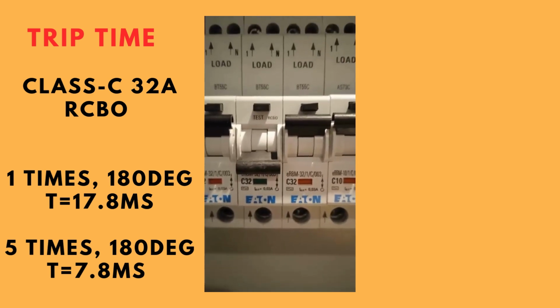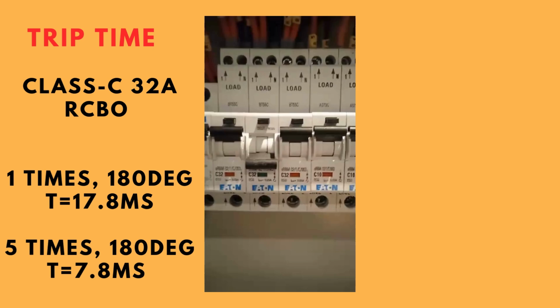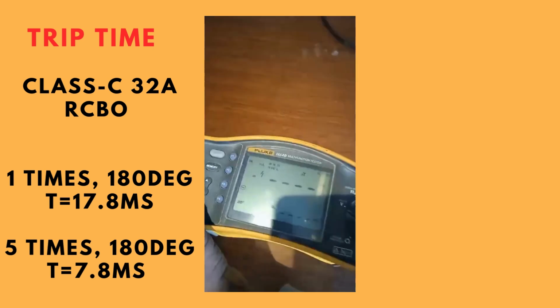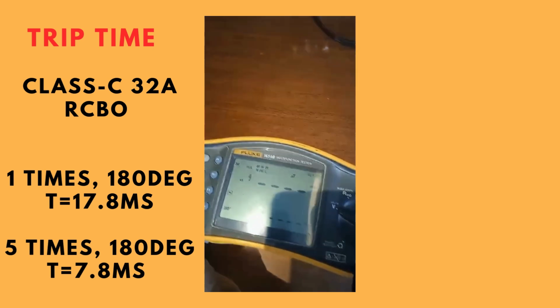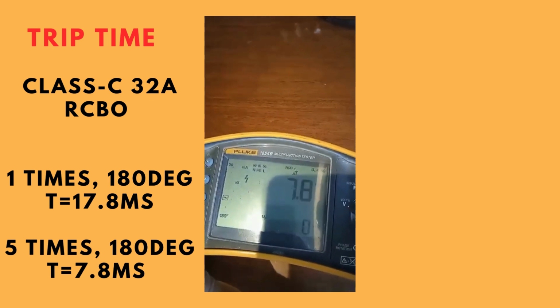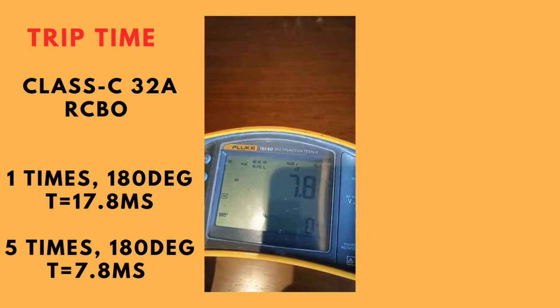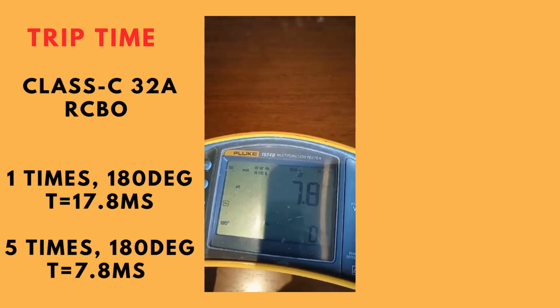32 amps class C circuit breaker. This is an RCBO. So we move back. Okay, so we are at times 5. It trips again at 7.8 milliseconds at times 5.